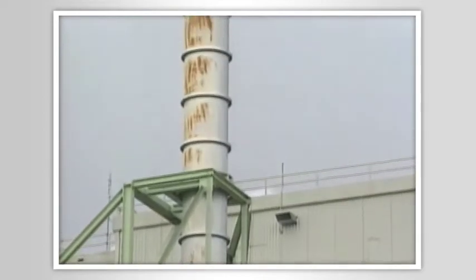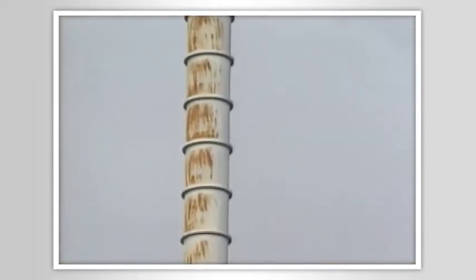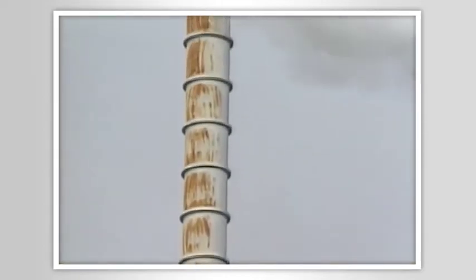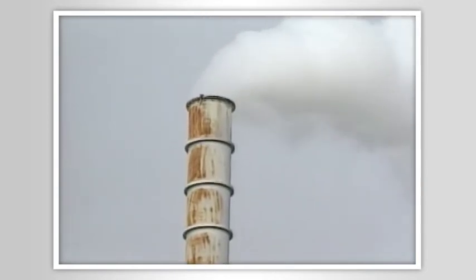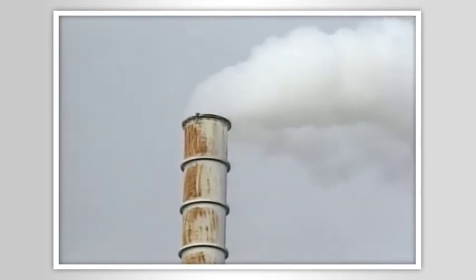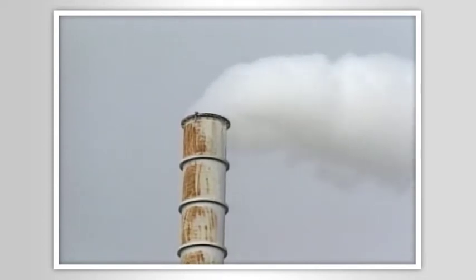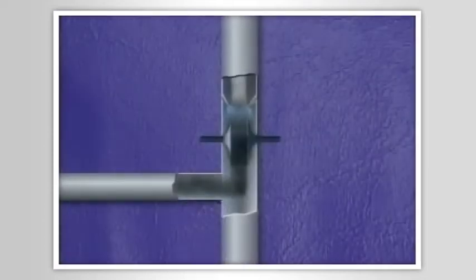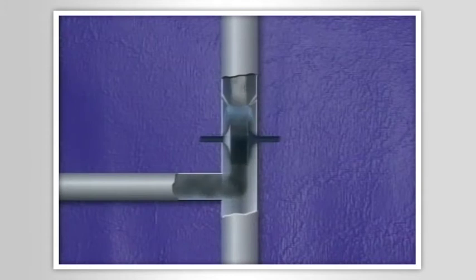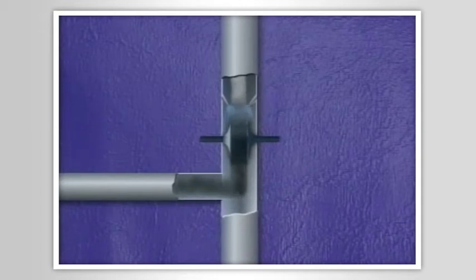This is a critical piece of equipment. It is used to remove solids from the gaseous emissions of a scrubber stack. Operating for more than just a few minutes without the fan would violate environmental regulations governing the site. So even though there are secondary systems, the failure of this fan forces a production shutdown.